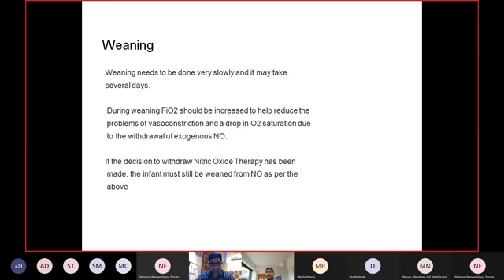So you need to ensure that, for whatever reason the ppm increases, the machine has the capability to know that, and immediately, apart from giving alarms, the machine should be capable of taking care and stopping the nitric oxide gas delivery. So when you are buying that product, you need to ensure that you are buying a complete system rather than just a gas delivery or a gas monitoring system. You should ensure that it is easy to use. At the same time, it should have all the components that you talked about.